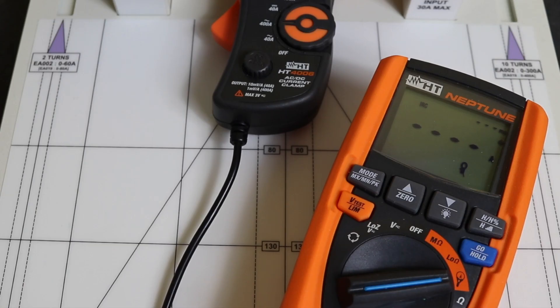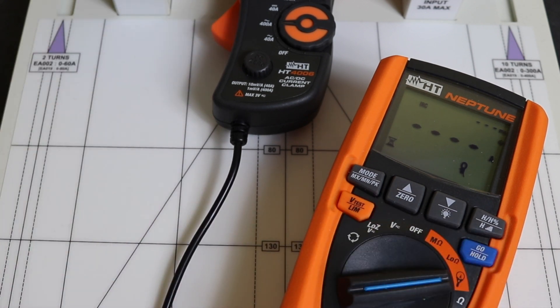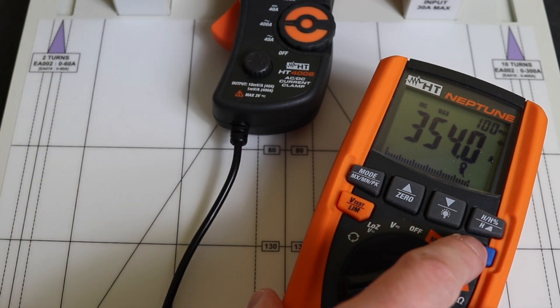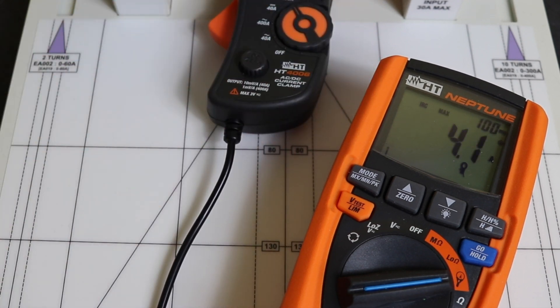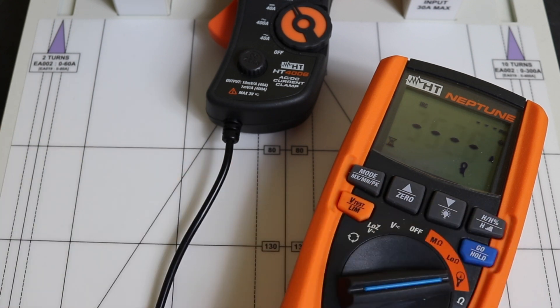Now with the HT Neptune instrument — set to 400 amp AC range, we inject 350 amps and get 354 amps, which is 4 amps above the injection level — all well and good. Hitting the go button to reinitialize and flipping to the 400 amp DC range, changing the test set to DC and injecting again, we get 352 amps. As per the first video, this instrument comes out as the most accurate for both AC and DC inrush measurements.